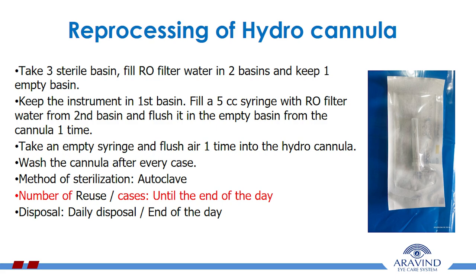Take 3 sterile basins, fill RO water in 2 basins and keep 1 empty basin. Keep the instrument in the first basin. Fill a 5 cc syringe with RO filter water from the second basin and flush it through the cannula into the empty basin one time. Take an empty syringe and flush air one time into the hydrocannula.